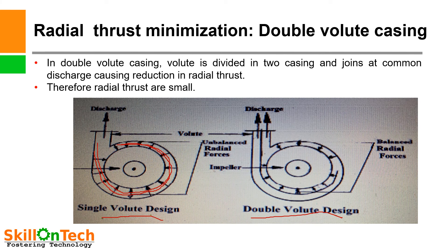In a double volute design casing, the casing is split into two parts and a ring is provided in the volute casing so that the area of the discharge path along the impeller is made uniform. Therefore, there is no pressure variation in the double volute design casing, and the residual radial thrusts are very small.